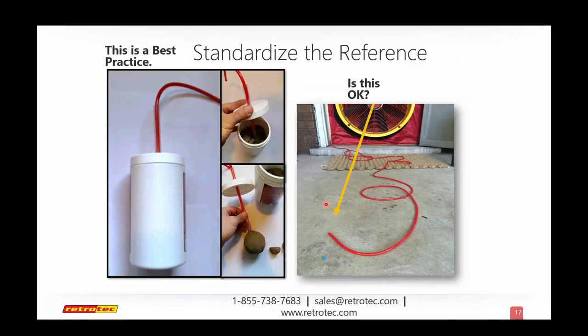really important point. Whenever you're doing a multi-point test, let's say you decide you're going to test from 25 to 75, go to the range you think you're going to be on, go to 25, go to 75, make sure you can get a reading. If you can't, you already know in advance that your software is going to tell you to change ranges. I remember I looked at a test once and the person changed ranges 5 times because they went to the very lowest range and then it ran out of juice and then it made them change ranges and so on. The test took forever. It's a really important idea when you're doing a multi-point test to take all of your test points on the same range, and it takes much, much less time when you do that. So that would be the first point.